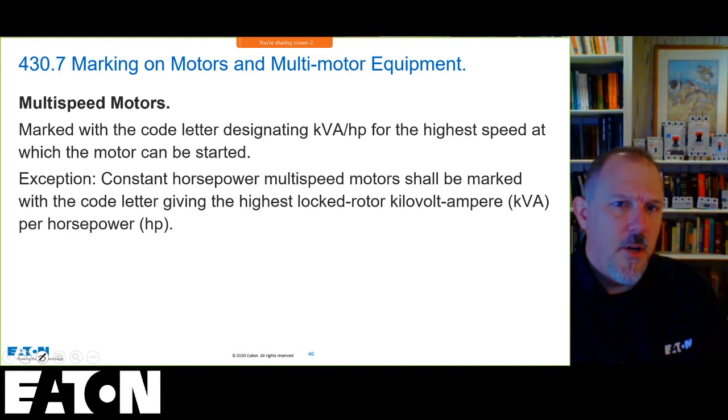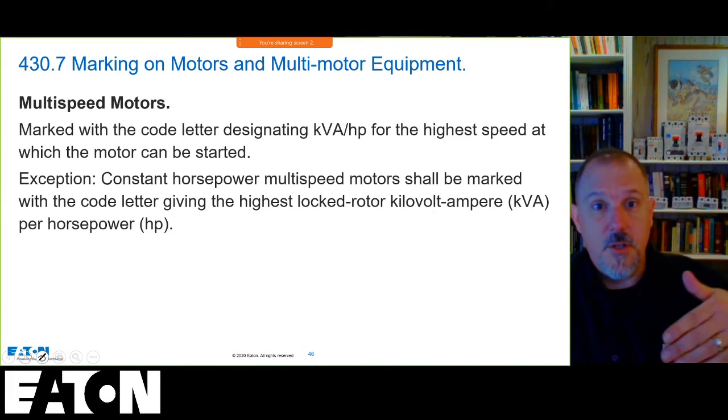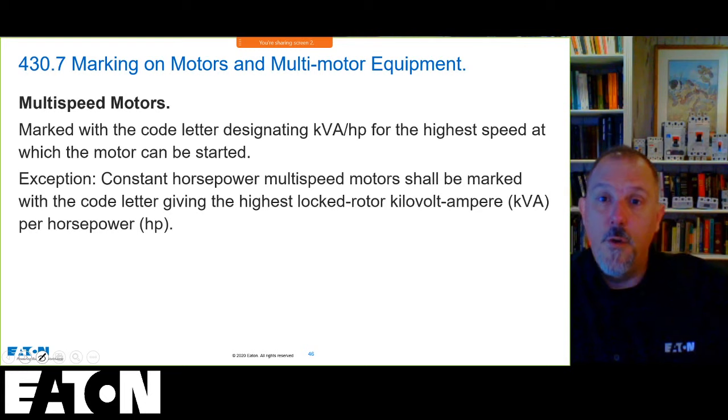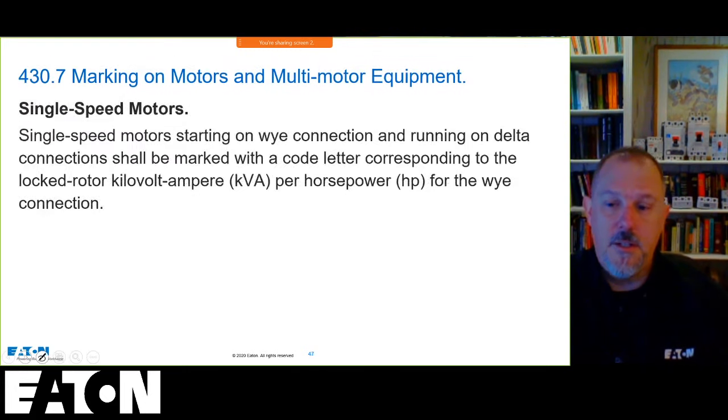So multi-speed motors, again, highest speed at which the motor can be started. So your kVA per horsepower is the highest speed, your constant, except for the constant horsepower. And this was, again, sometimes your locked rotor amps, your full load amps, are going to be greater when you're in these multi-speed applications.